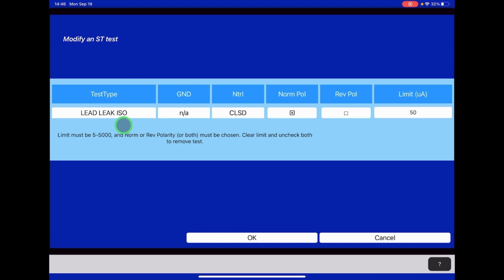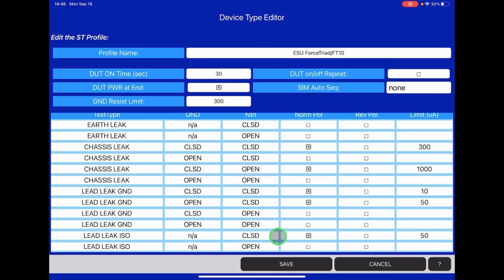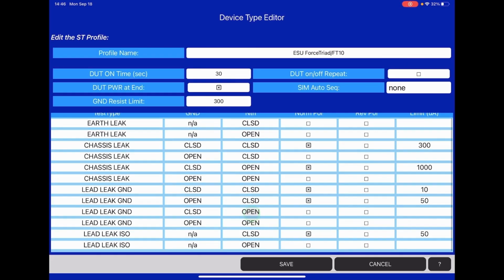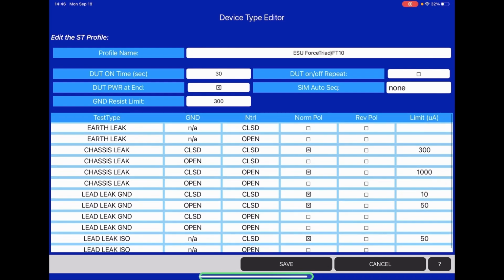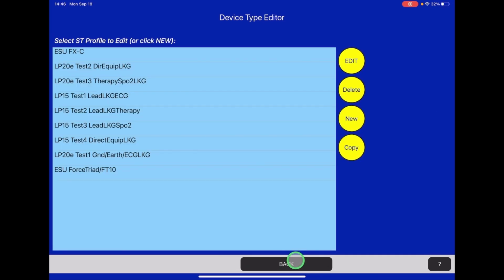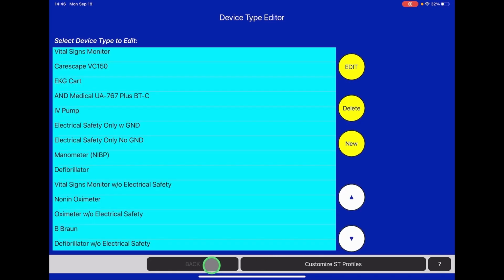There is a 120 k ohm resistor limiting the current for safety protection, but you're still energizing that high voltage, so you want to be careful and make sure you don't touch those leads. We're going to do this with the neutral closed in normal polarity, and the limit here is also 50 microamps. So we've made sure we configure our test the way we need to, and we can save this, and it will get saved into our library of available procedures you can utilize on the app.